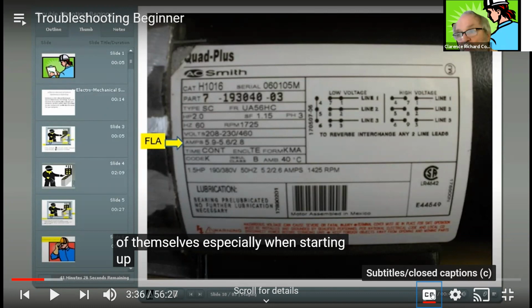If you're at 2 amps, for the heater sizes, you're going to have to adjust that to 2 amps. If your heater kicks out above 2.8 amps, that means you might end up burning it. If the heater kicks out below 2 amps, then you're going to have nuisance tripping. So having that sized correctly gets important. That's FLA. You hear us talk about FLA, full load amps, meaning you've got full load on the motor, which is going to give the amperage of 2.8.